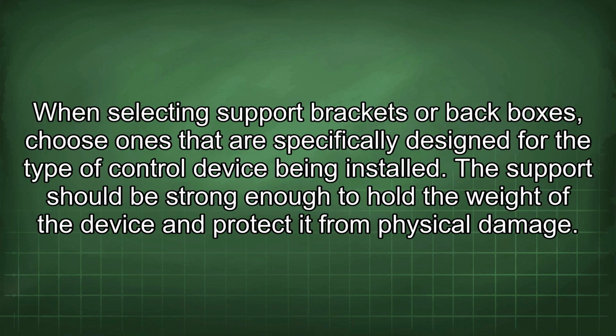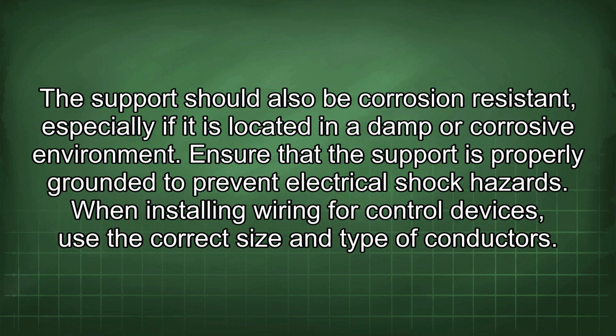When selecting support brackets or backboxes, choose ones that are specifically designed for the type of control device being installed. The support should be strong enough to hold the weight of the device and protect it from physical damage. The support should also be corrosion resistant, especially if it is located in a damp or corrosive environment. Ensure that the support is properly grounded to prevent electrical shock hazards.